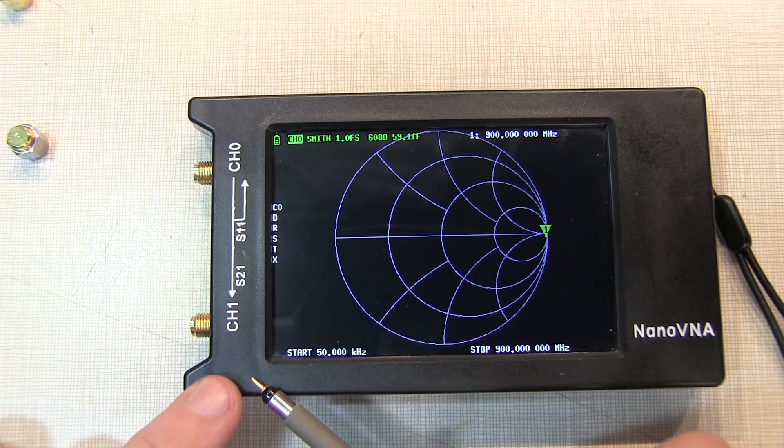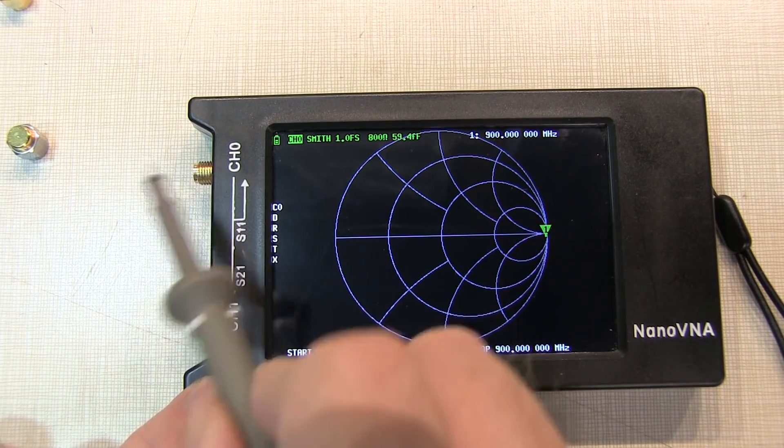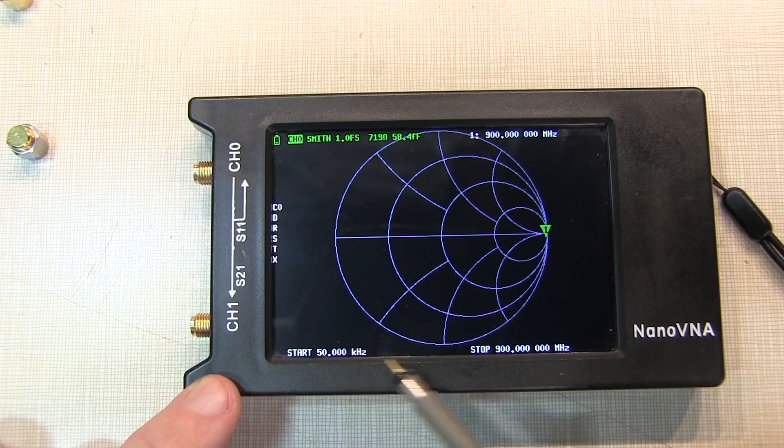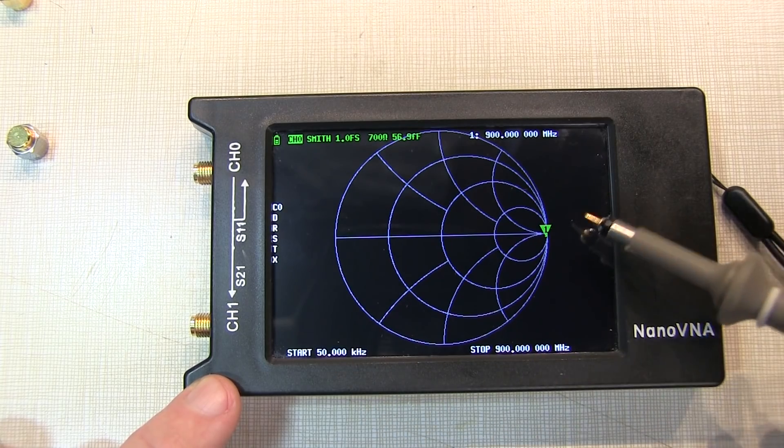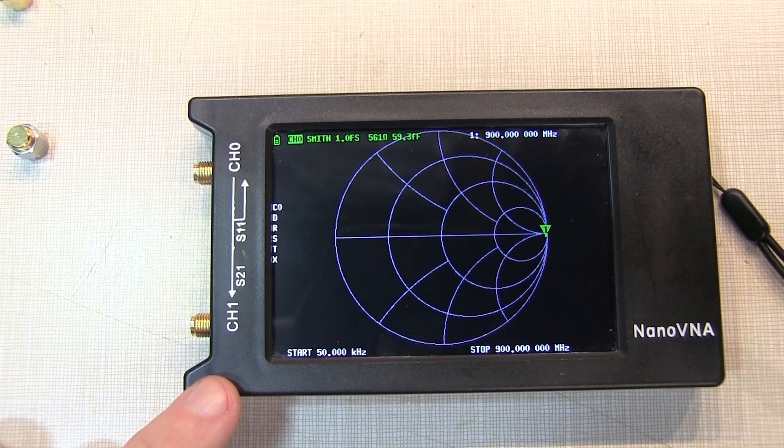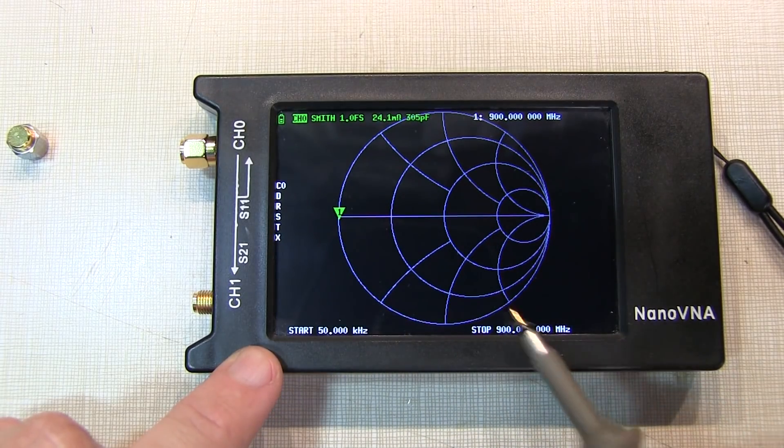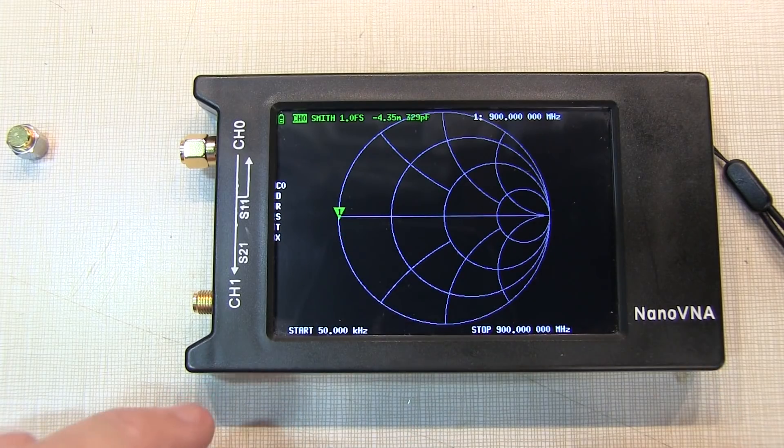So here I've got the Nano VNA powered up using the default calibration. And I've got nothing connected to the input. And we can see that our measurement point over this 50 kHz to 900 MHz frequency range is way out over here, which indicates that it's a pure open circuit even over this 900 MHz frequency range. Now if we connect a short circuit to channel 0 here and take a look at the Smith chart, we can see that for this whole 900 MHz frequency range, we're sitting right there at the short circuit position on the VNA.